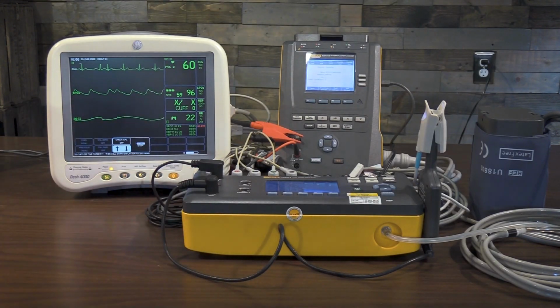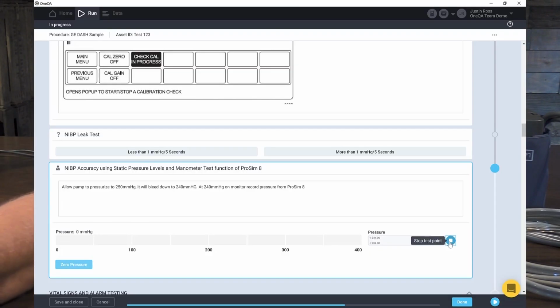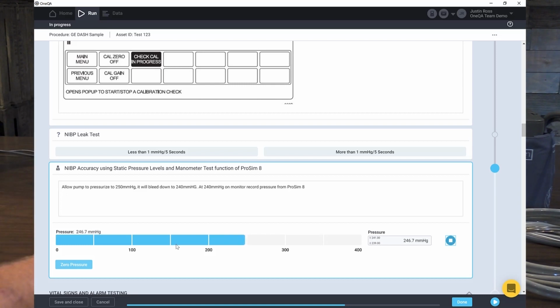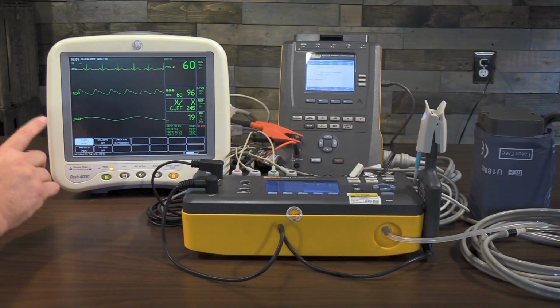All right, it beeped. That's done. Now we're going to go ahead and hit start right here. Run test point, and we're going to start on our monitor. Now the monitor is going to pump up, and we'll see the pressure build right here in OneQA. Remember, you never want to calibrate a monitor using a dynamic blood pressure. You want to use it as a static, solid pressure. So that's what we're doing here. This OneQA and ProSim 8 is also capable of doing leak checks, the pop-off valve check, as well as has a built-in pressure source. But the GE monitor doesn't need those things. It just needs the manual method to do the cal check like this.